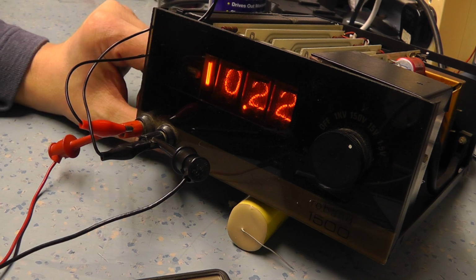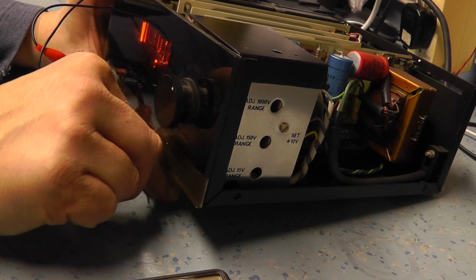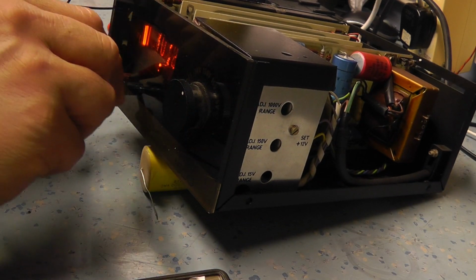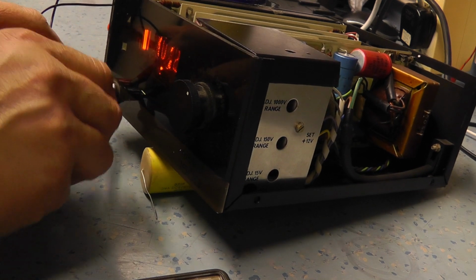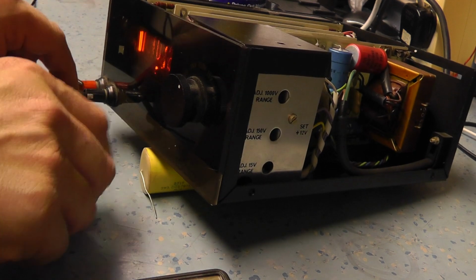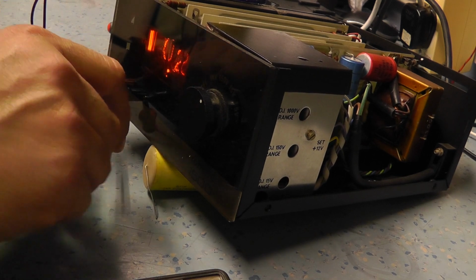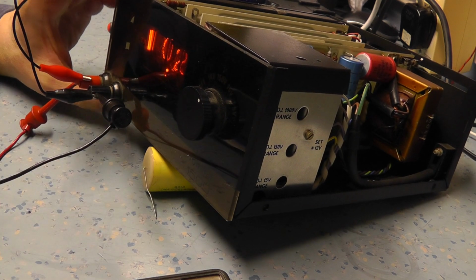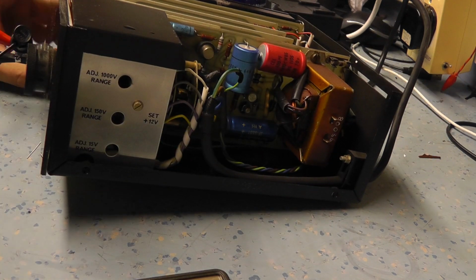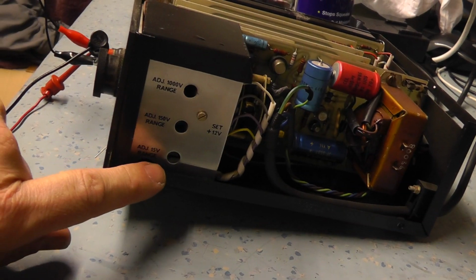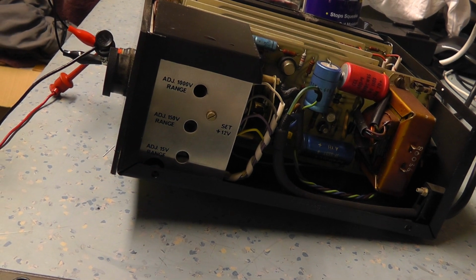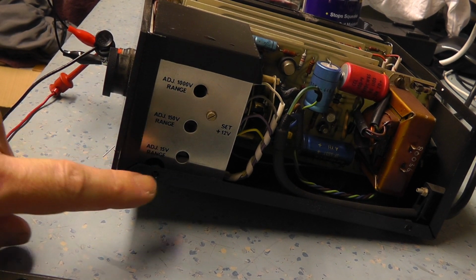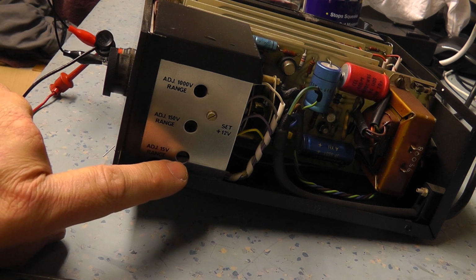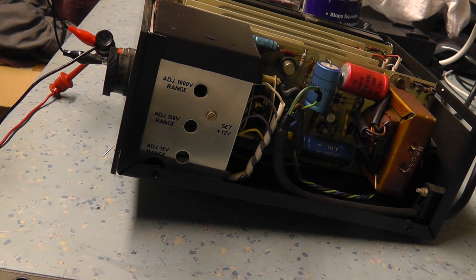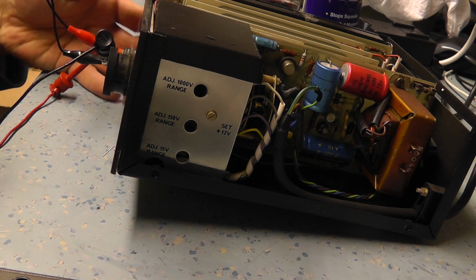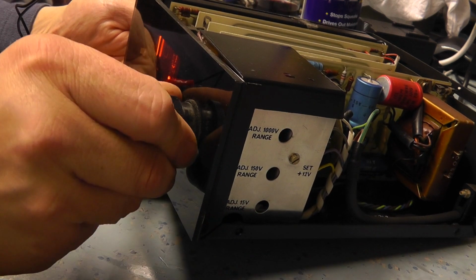Now these are fairly straightforward to correct. So what I'm going to do is make an adjustment on the control and get the thing to stay on this so I can measure it properly. Okay, so the adjustments are on the front side panel here. So we're on the 15 volt range. Are we on the 15 volt range? Yeah, we are on the 15 volt range, so that's the adjustment here. So we could adjust that fairly straightforwardly. What I will do is check it on the 15 volt range as well, and the 150 volt range.